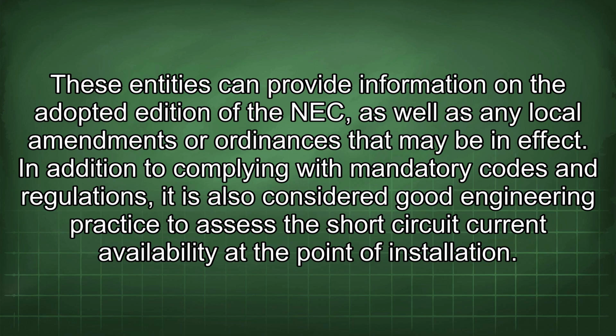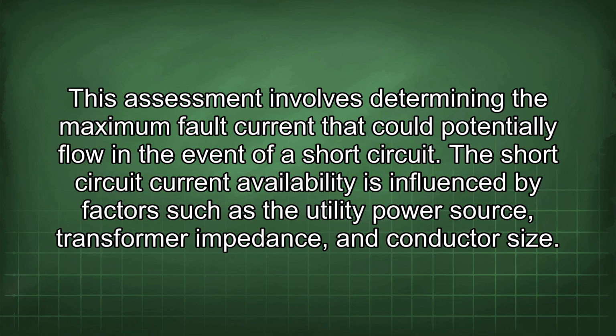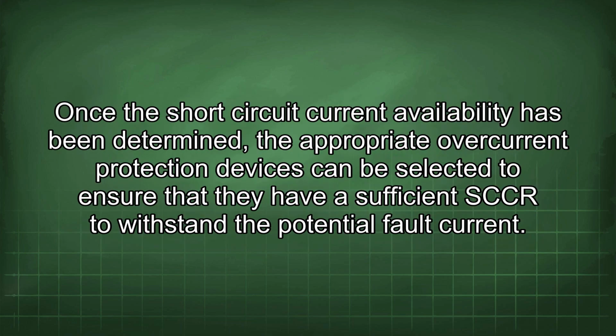In addition to complying with mandatory codes and regulations, it is also considered good engineering practice to assess the short-circuit current availability at a point of installation. This assessment involves determining the maximum fault current that could potentially flow in the event of a short circuit. The short-circuit current availability is influenced by factors such as the utility power source, transformer impedance, and conductor size. Once the short-circuit current availability has been determined, the appropriate overcurrent protection devices can be selected to ensure that they have a sufficient SCCR to withstand the potential fault current.